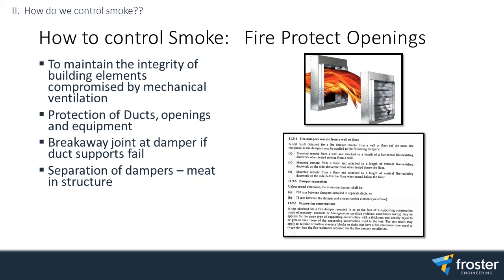That's right. We talked about the breakaway joint here, which is critical. That's another one. So we might have a fire-rated riser we're coming out of with exhaust ductwork. Could have 2 or 3 ducts coming out of a riser, picking up, say, 3 toilet compartments on a floor or between floors. But our air quantity is extremely low. It could be 200, 300 liters a second. So the size of that duct could be 200, 250. Now, say I decide, okay, I'll put the duct here. I've got a fire damper in that duct. The duct is 200 wide.